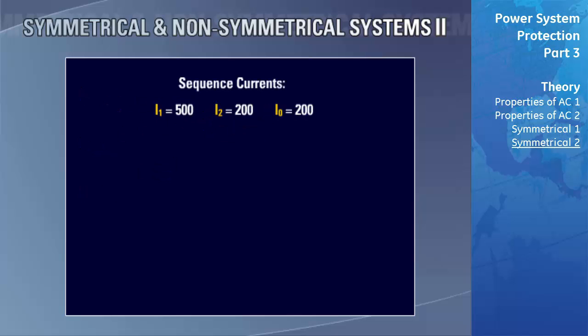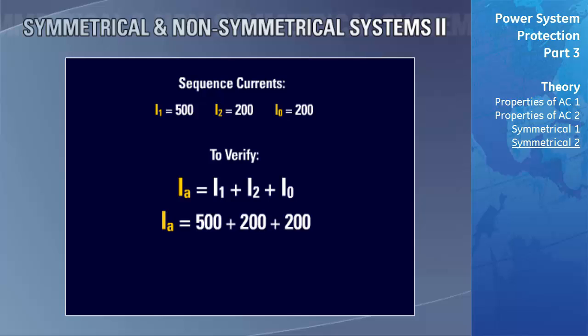To verify our calculations, we use the predetermined positive, negative, and zero sequence current values to recalculate the actual current on phase A at the time of the fault. Ia equals the positive sequence current plus the negative sequence current plus the zero sequence current: 500 + 200 + 200 = 900 amps — which matches the actual current measured on phase A by the GE Multilin SR-760. Modern microprocessor-based protective relays use symmetrical components to calculate positive, zero, and negative currents and voltages from CT and PT signals, and these quantities are then used by the protective elements within the relay.